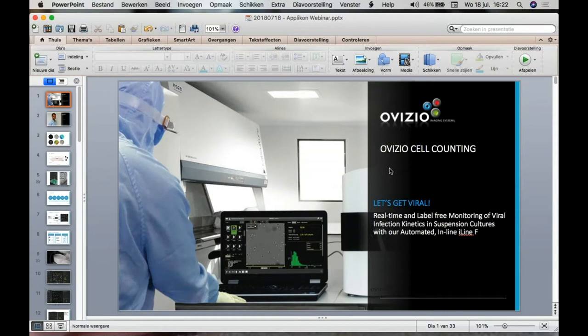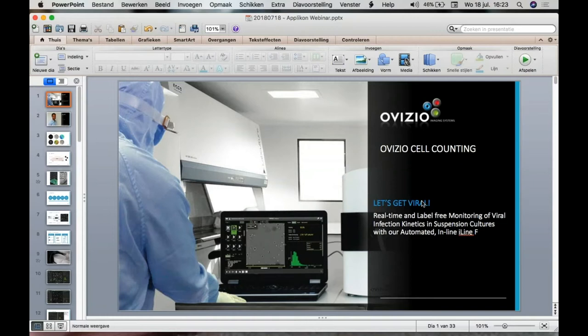Question: What is the biggest cell you can measure? We can measure all mammalian and human cell types, and even smaller towards insect cells — yeast is also possible. Everything within that range is definitely possible. If cluster formation happens, clusters up to a maximum of around 10 cells that are more or less monolayer and don't form a 3D formation shouldn't be a problem. Anything bigger than that, or anything smaller like bacteria, is out of our limits.